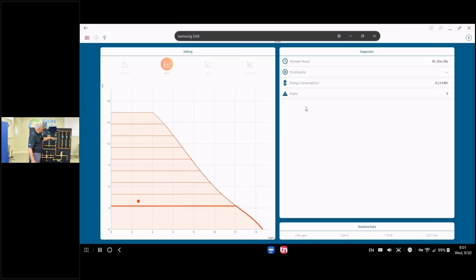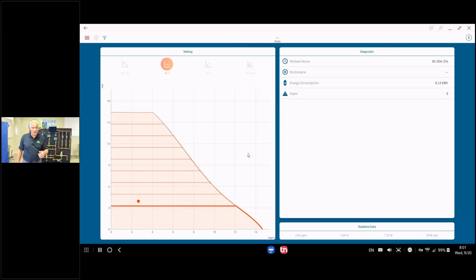What we have going on now is a constant pressure system because it's a zone valve system, and that's where we want to set it. So if we're looking here on the screen, let's see if I can get this to work. Should be on. There we go. So if I look here, you'll see that right now the system is operating just above 3 feet of head, maybe 3.5 feet of head, and it's operating at basically maybe 2.5 GPM.